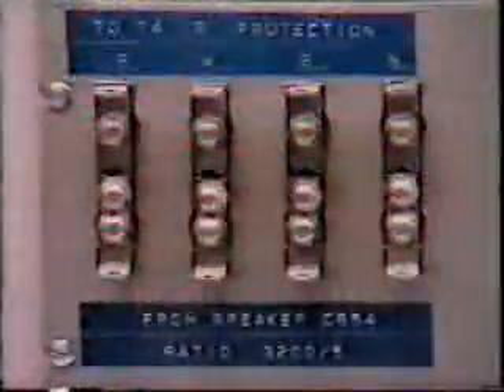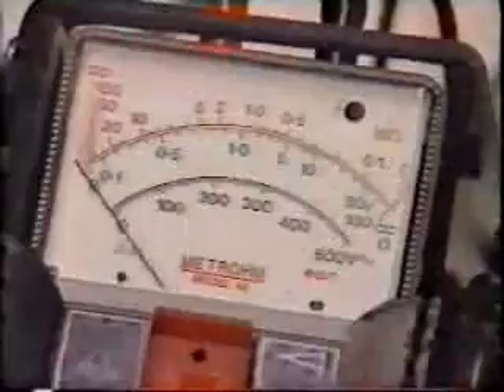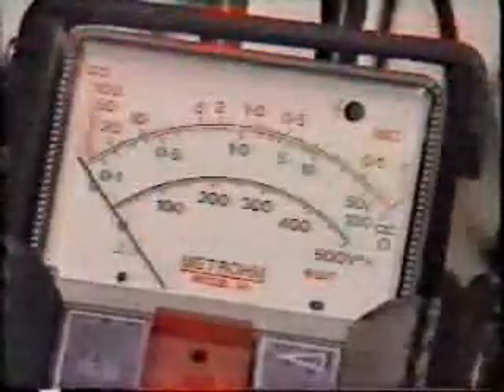Insulation resistance, that is, IR tests, must be carried out usually in conjunction with the contractor. Before commencing IR tests, make sure that the wiring is isolated, that is, no equipment is connected. Also ensure that all wiring grounds are removed. Check the insulation to ground and between each separate circuit. The insulation resistance varies, but should be between 1 and 10 megohms using a 500-volt megger.